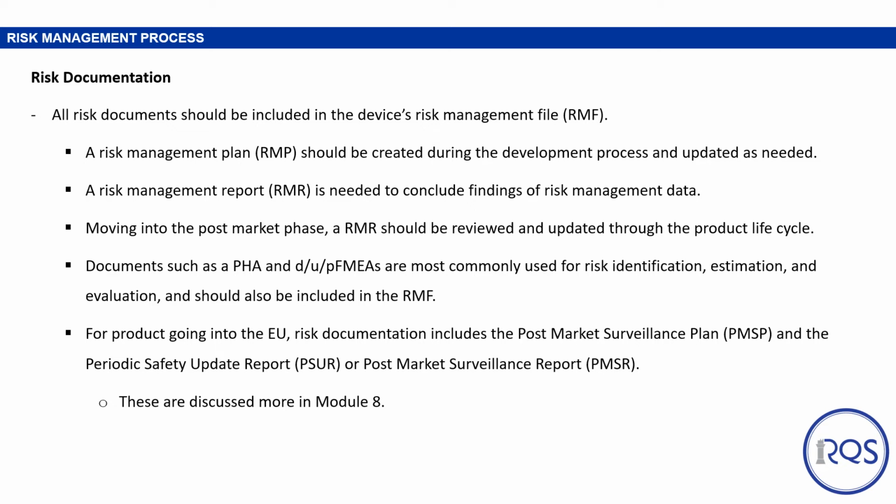So let's now review some of the key documentation that's needed for risk management. All risk documents should be included in the device's risk management file, or RMF, and there should be a risk management plan, or RMP.